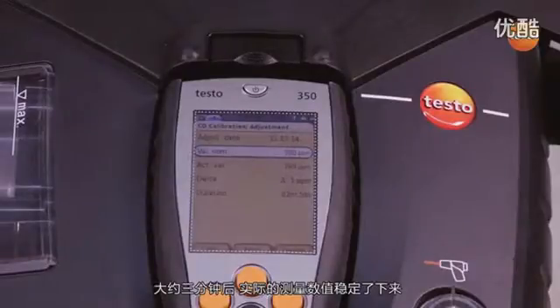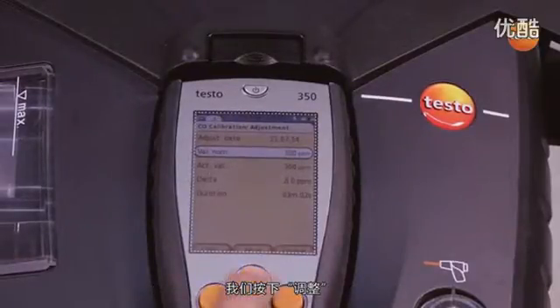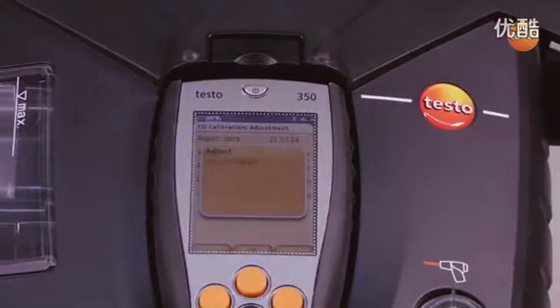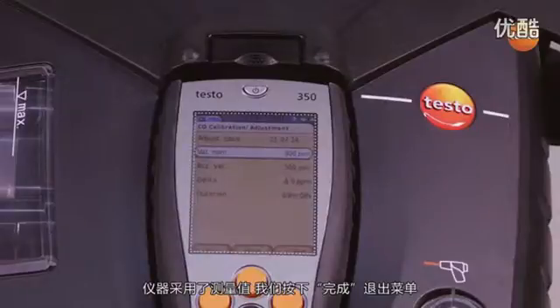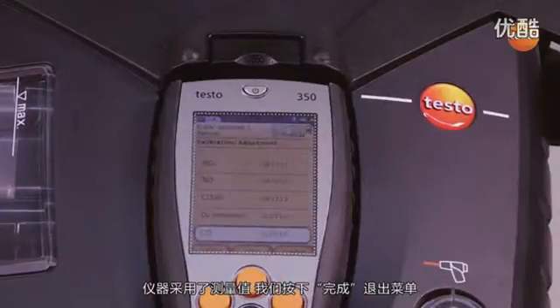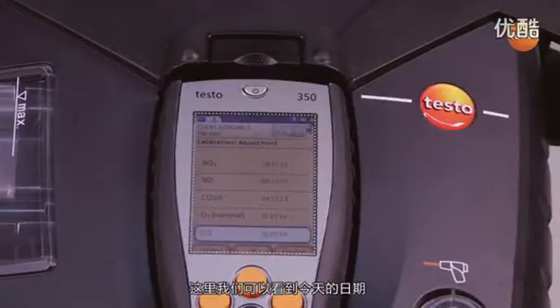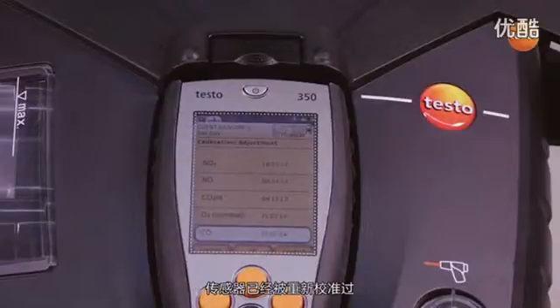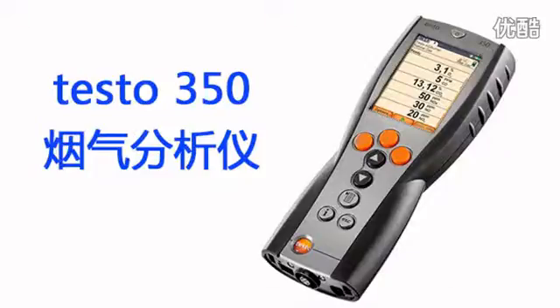When the actual value has stabilized, in our case after 3 minutes, we confirm the application of the calibration with adjustment. The measurement values are taken over and we exit the menu with Finish. In this case, we see today's date and the sensor is readjusted.